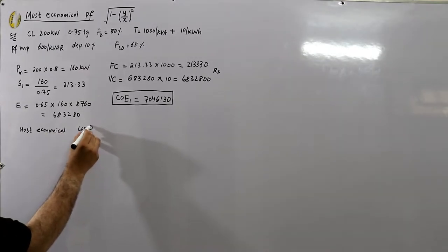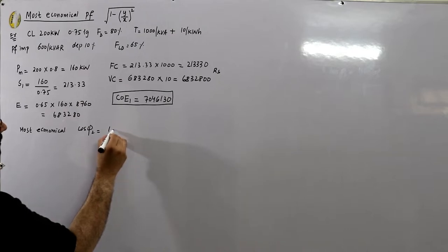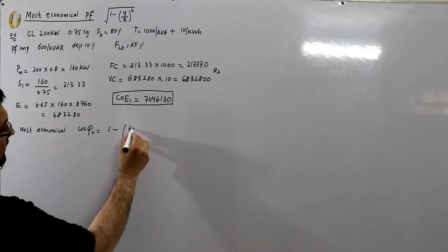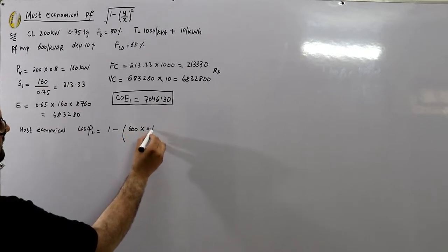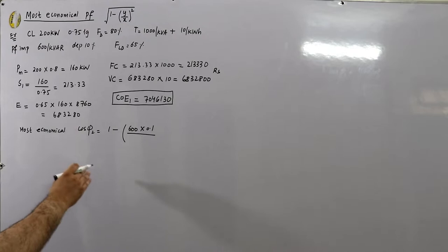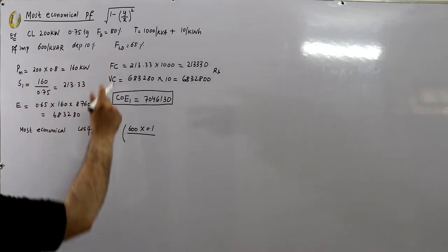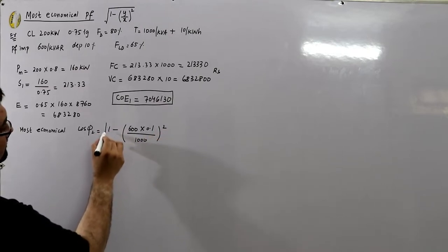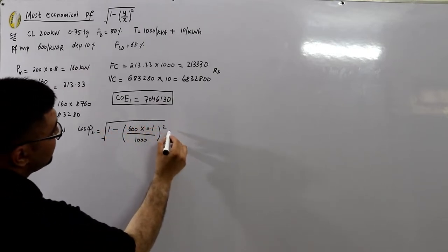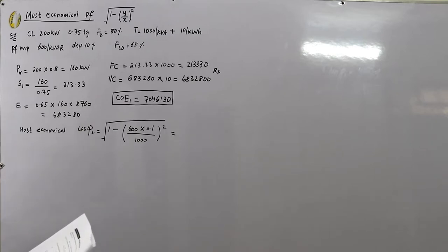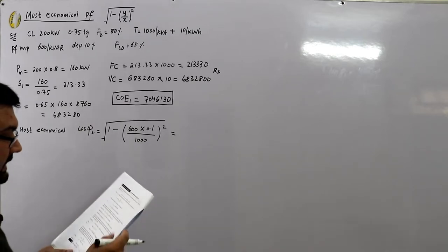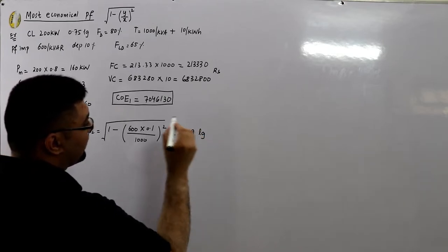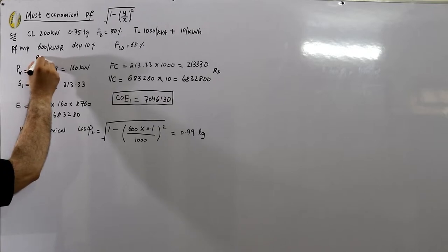Now determine the most economical power factor. The formula gives cos φ₂ = square root of 1 minus (y/x)², where y is the cost per kVAr which is 600 with 10% depreciation, and x is the tariff per kVA which is 1,000. This gives the most economical power factor as 0.99 lagging.